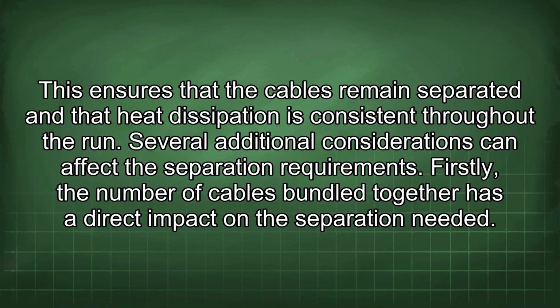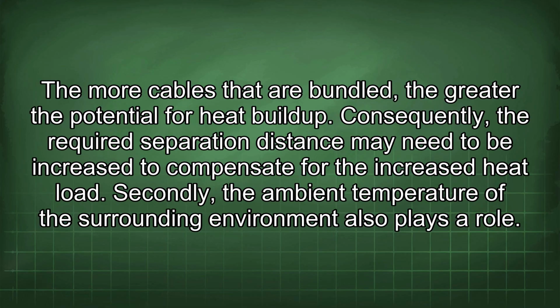Several additional considerations can affect the separation requirements. Firstly, the number of cables bundled together has a direct impact on the separation needed. The more cables that are bundled, the greater the potential for heat buildup. Consequently, the required separation distance may need to be increased to compensate for the increased heat load.